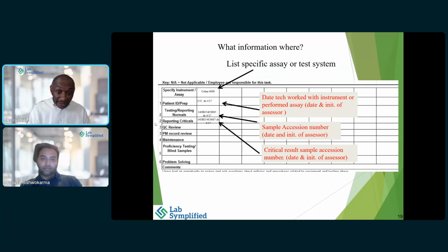There are some kits out there that are still just a swab. When you do the same thing, then it's a colorimetric test. It's going to show up positive and negative. That is something you need to discuss. If there's any ambiguity you're not sure about, you need to discuss it with your medical director, because he or she is responsible for the laboratory. If you want to group some tests together and say, hey, this is a test system, nothing changes, that is fine. So the simple, quick answer is usually test platforms, you have one big modular or whatever, that's just one test system.